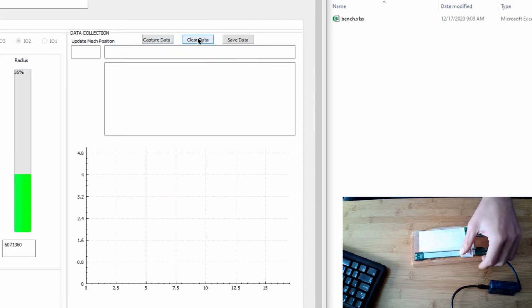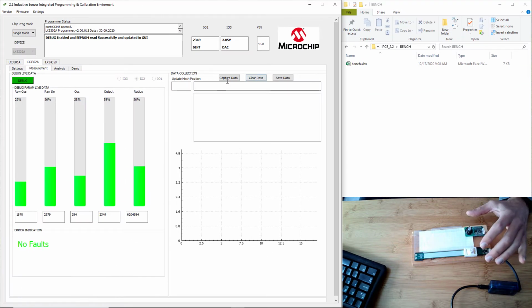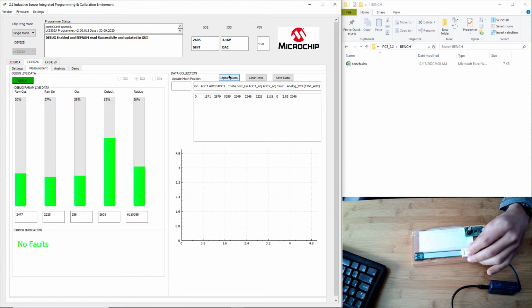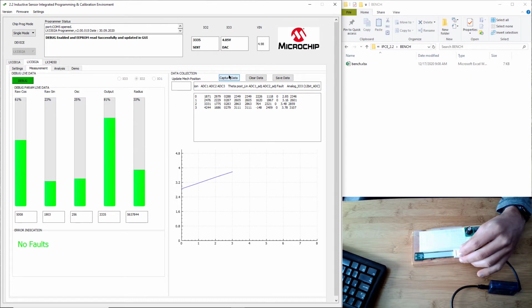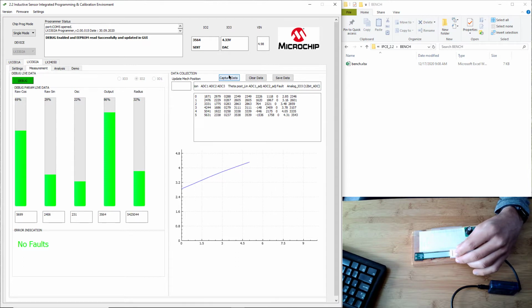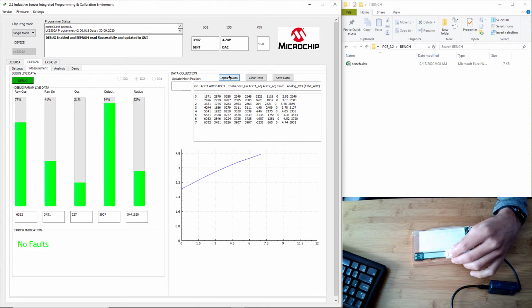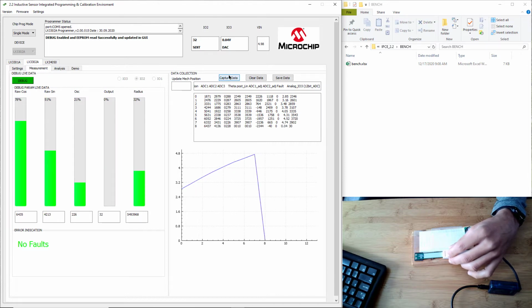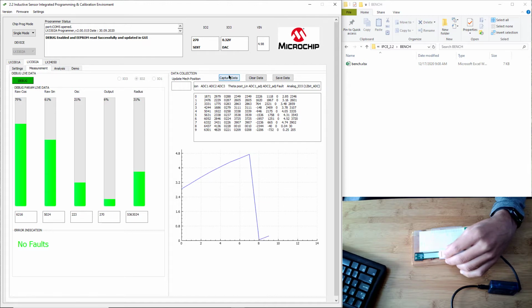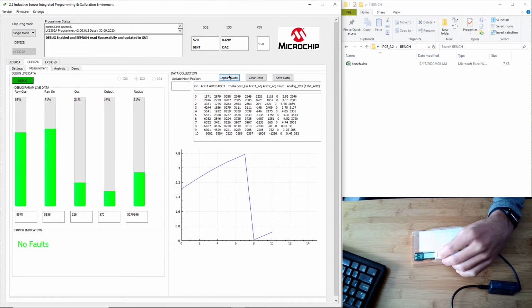the measurement range. I'm going to do a slightly different technique, which I will show you. As long as you capture fixed mechanical intervals, this will be an equivalent way of doing the same thing. So I'm still moving the target at fixed intervals, but I know those intervals are 6.33 millimeters, and I can just map those later if I want to. All the procedures that we do today will work with fixed interval data in addition to absolute mechanical position data too.